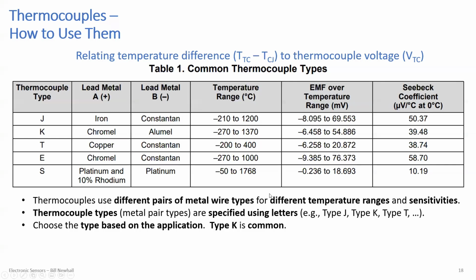You choose the type based on your application, your temperature range, the sensitivity you have, maybe the amplifier you have to amplify the thermocouple voltage. Type K is a really common one. Honestly, I don't really know why, but it has a pretty good range, and you'll find them anywhere. If you've bought a multimeter that came with a temperature measurement capability, it usually comes with a temperature probe that is a thermocouple, and it's usually a type K thermocouple.